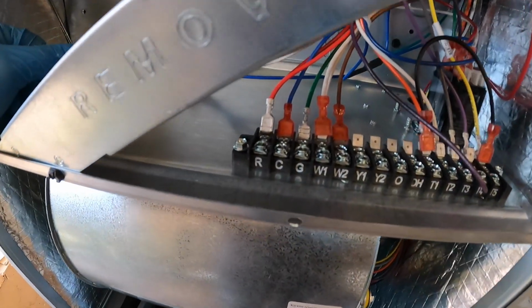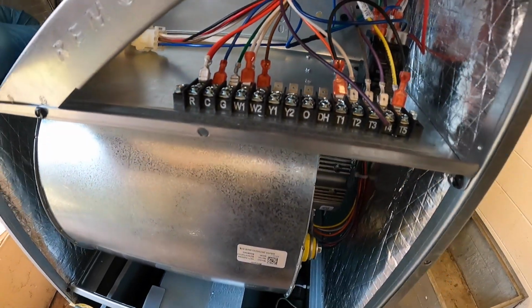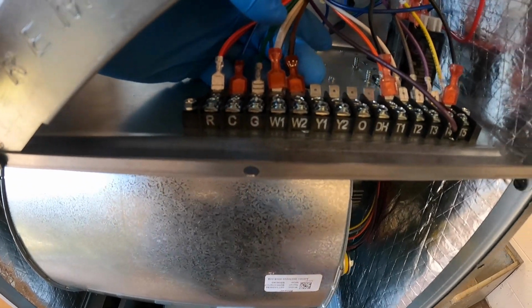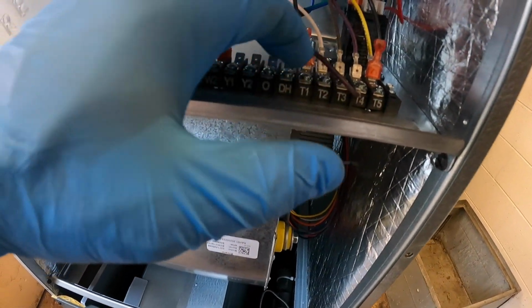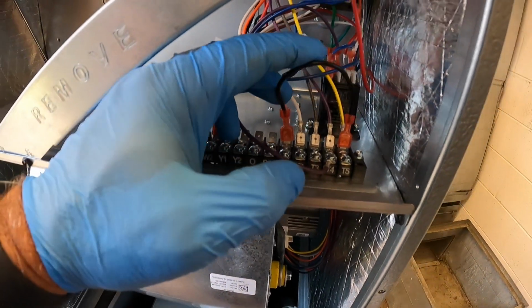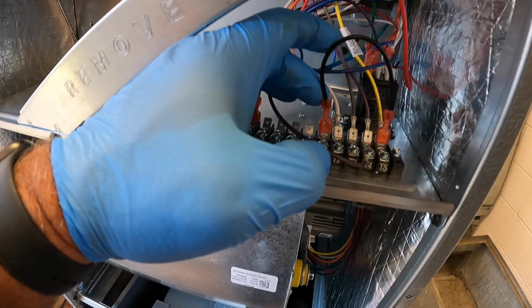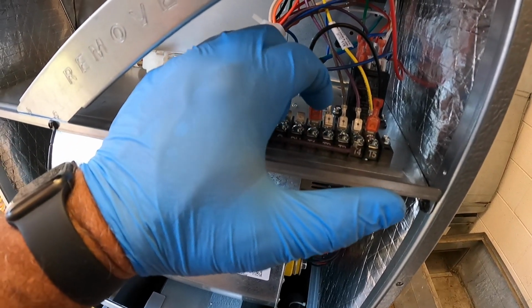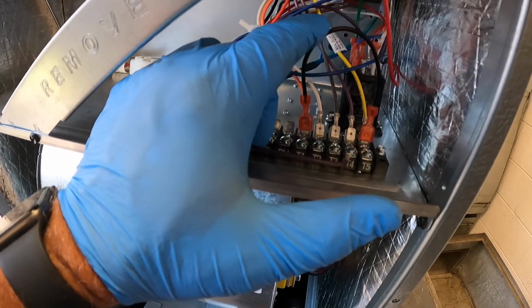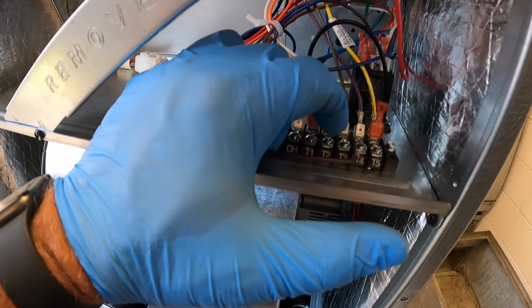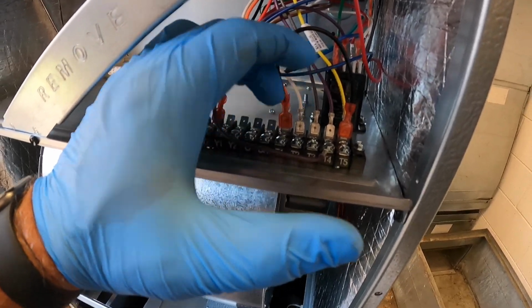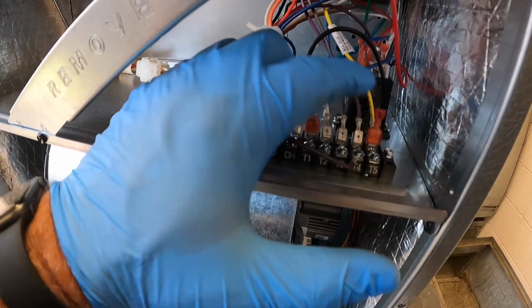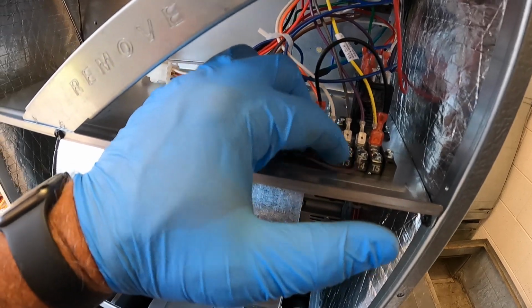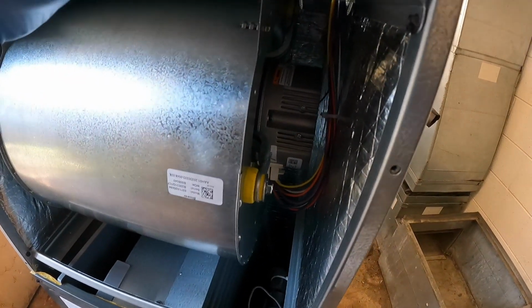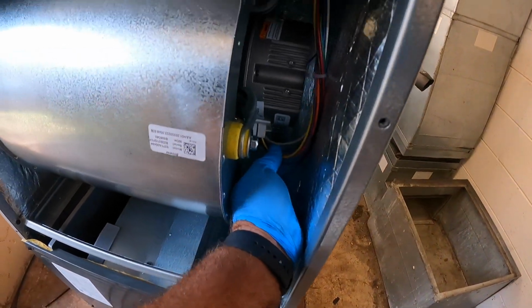And the big difference is, of course, this big terminal strip. They've got your thermostat hookups right here, but they've got the speed taps for your fan right over here. And apparently this black jumper here can be moved like it is right now. You've got speeds 1 through 5. If you move this jumper and put it on the same terminal as you're putting your tap wire, either 2, 3, 4, or 5, it'll give you 9 distinct speeds on a normal 5-pin motor here.